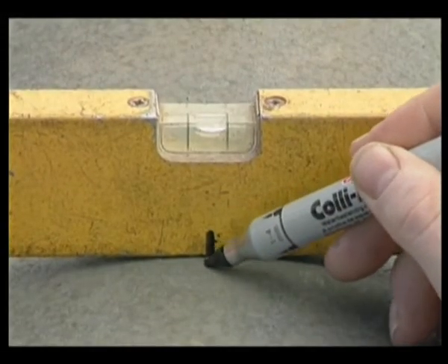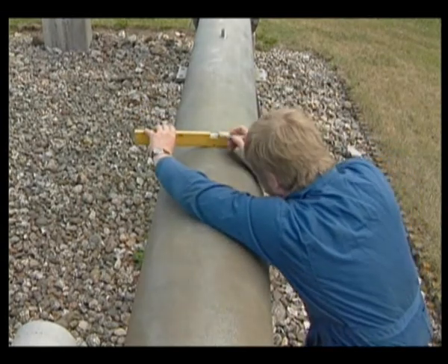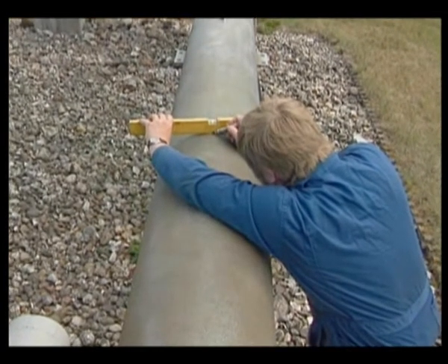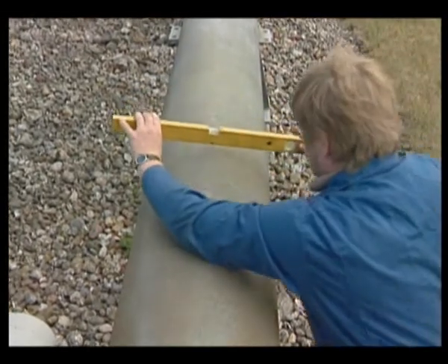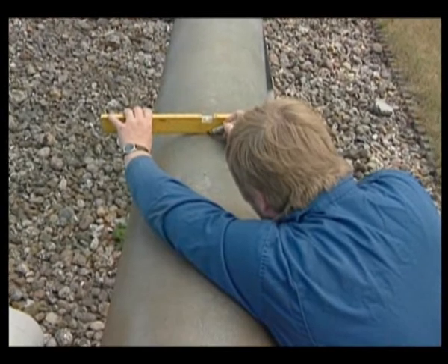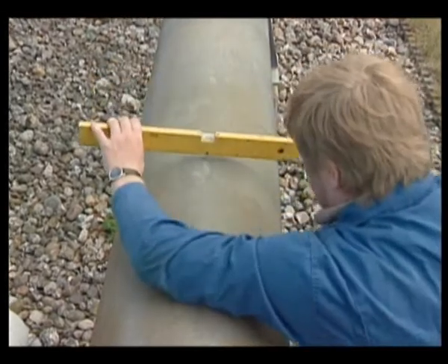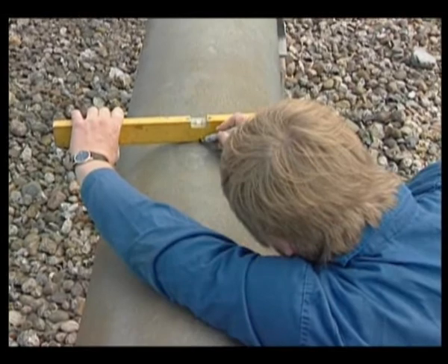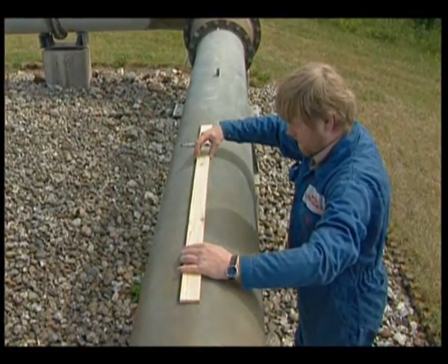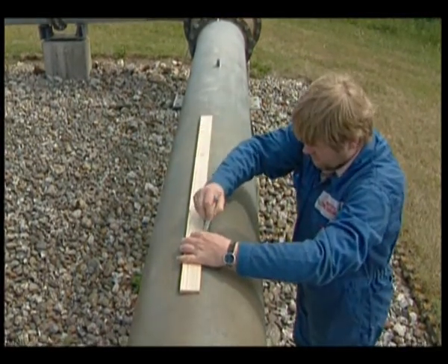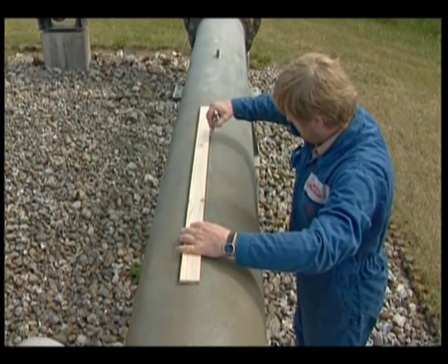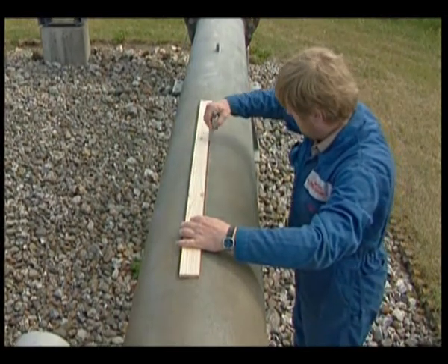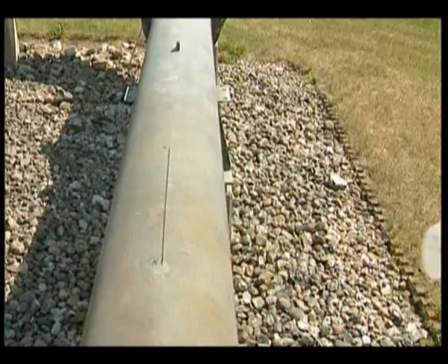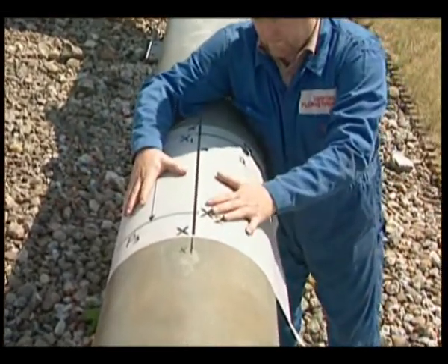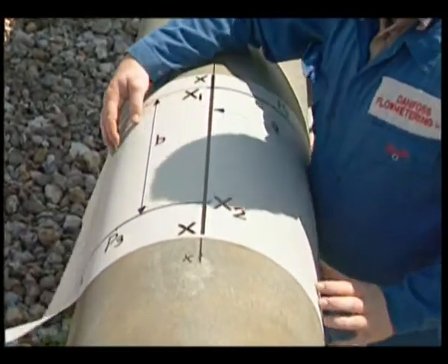To place the drawing correctly on the pipe, we must find the top line of the pipe. This is done as shown here with a level instrument. Draw 4 to 5 marks on the top of the pipe. Then draw a line through the marks you've drawn. The top line has now been found. The drawing can now be placed on the pipe. Note that the line XX on the drawing must coincide with the top line of the pipe.